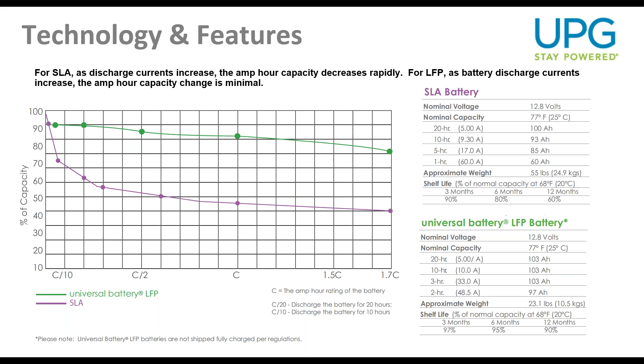What we've done is documented how, as discharge currents increase for an SLA battery, the amp hour capacity decreases rapidly. An SLA starts at 100% but quickly discharges to about 40% capacity, or 60% depth of discharge. An LFP battery starts at 90%, since they're never fully charged per shipping regulations, but the discharge only goes down to about 75%. This is a perfect example of how LFP compares to SLA in the field.